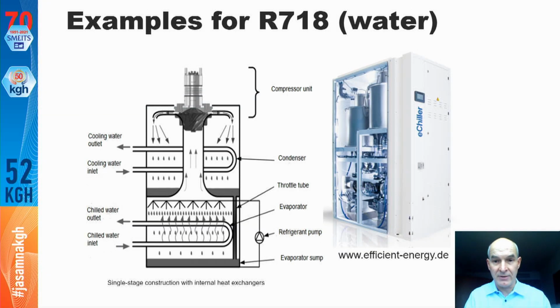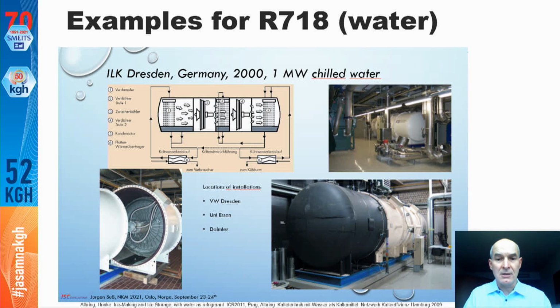Here is an example of a data cooling chiller from a supplier producing this kind of compact system. On the other hand, there are larger sizes, like this example from ILK in Dresden, a 1 megawatt chiller unit installed in several industrial applications across Europe. This is possible, it takes a bit more space, but it is very efficient.